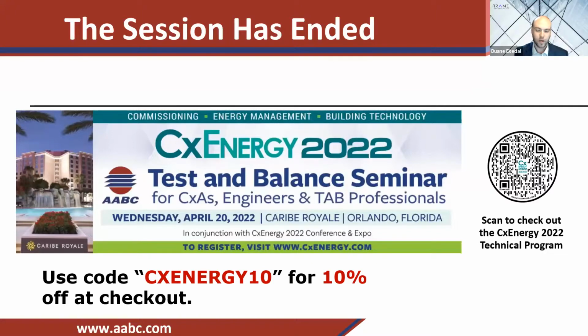Yeah, sorry. So ideally, it's going to be to the extent that's going to accomplish the design intent, right? So typically it's going to be the entire system if you can. The only way that you really can get there effectively is through analytics. So it's a combination of on-site verification and remote verification a lot of times to get to that 100%. So maybe a sampling of 10-20% on site, and then you're sampling the rest off-site through analytics, unless the first sampling yields results that need further investigation. But ideally, you want to sample the entire system if possible.